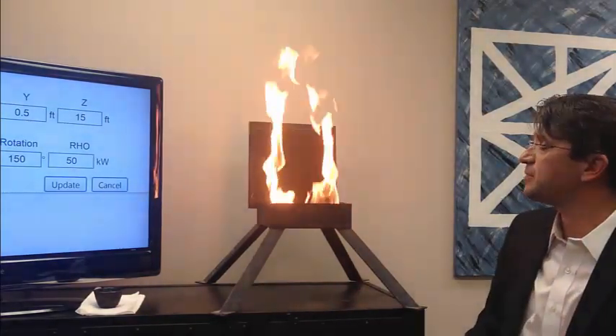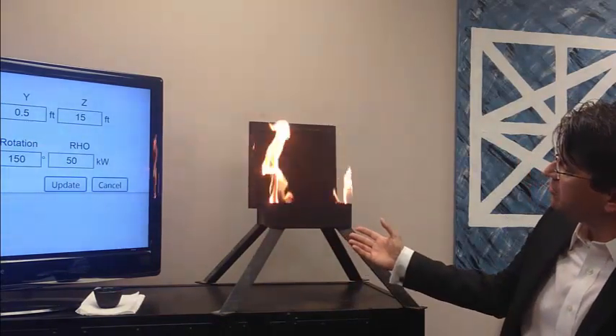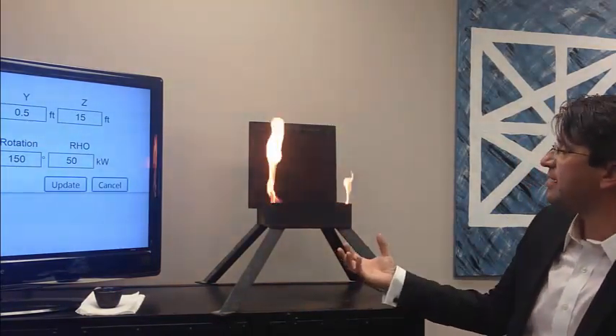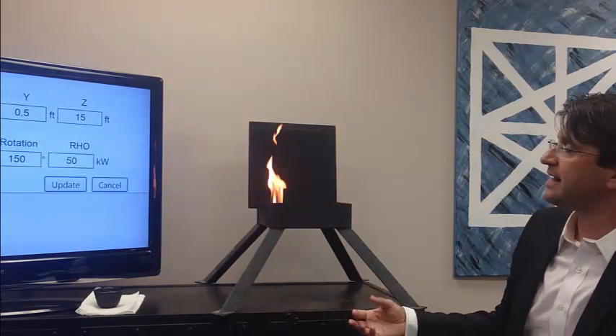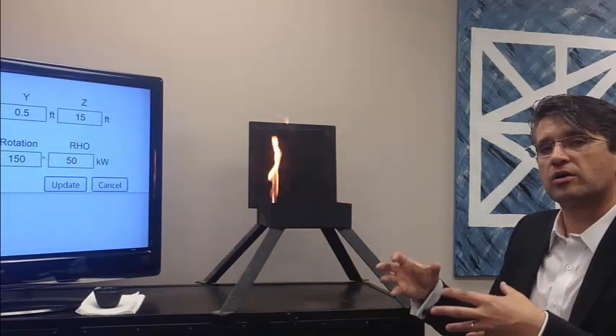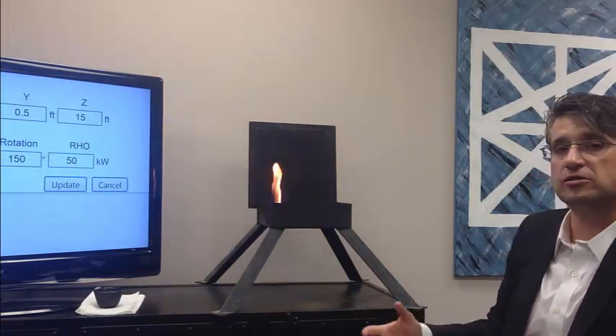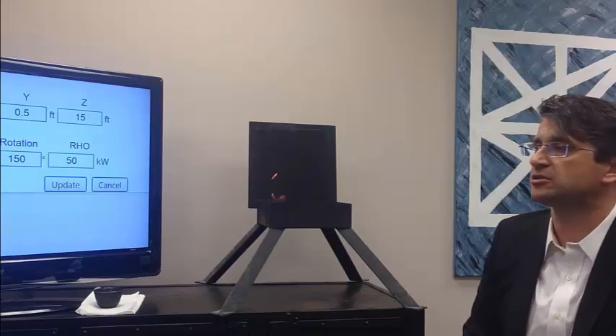And it's an important parameter in the fire and gas mapping because the smaller the fire, the harder it is to detect. And that would require more detectors that are more closely placed together than if you were looking for larger fires, which are going to be easier to detect.